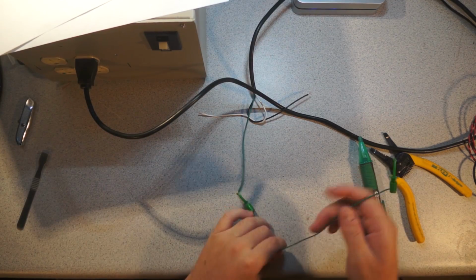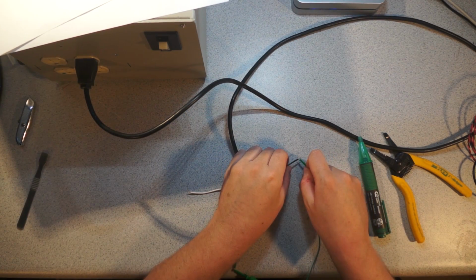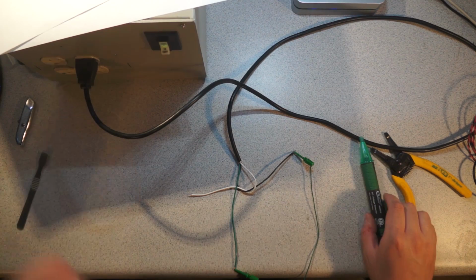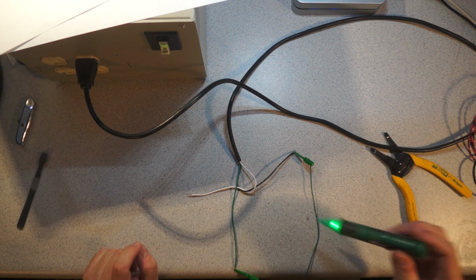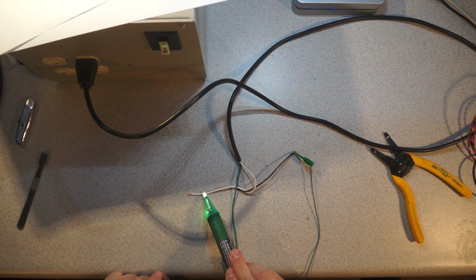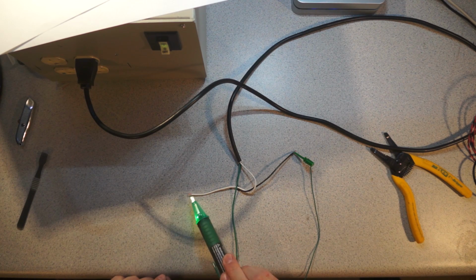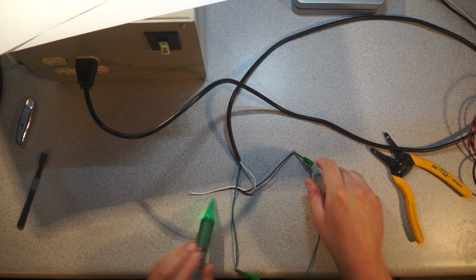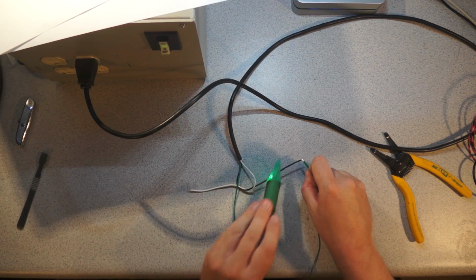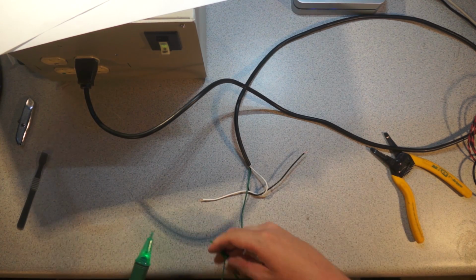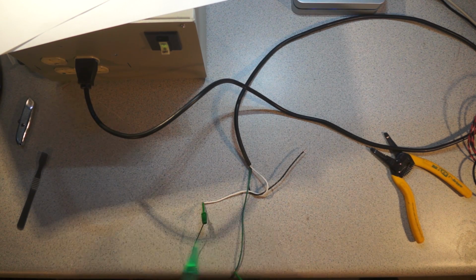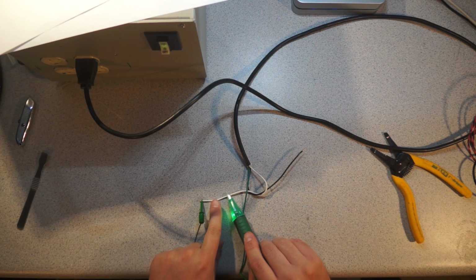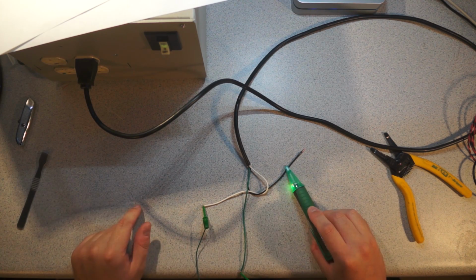So what we'll do here is say let's ground the traditionally hot. It comes up without any problem. You can see now there's nothing there, but the hot is triggering my voltage detector. If I get that on the clip there and then go over here, now the neutral is safe and the hot is hot.